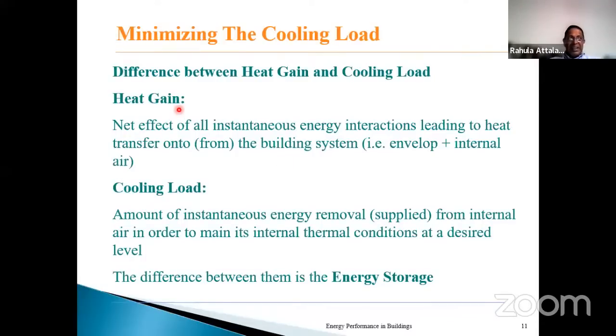And therefore, the normal thinking is that heat gain should be equal to cooling load, because what is coming into the building should be removed. But it is not true. These two are different. Sometimes heat gain might be larger than cooling load. The difference comes from the energy storage in the building envelope, because the building envelope has certain material that can store energy. Therefore, what comes into the building is, without being added to the air, stored by the building structure, and it will release depending on the situation from time to time. So essentially, part of the heat gain by the building will be stored or released depending on the time, and only a fraction will go into the interior.